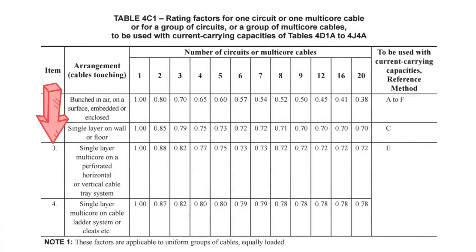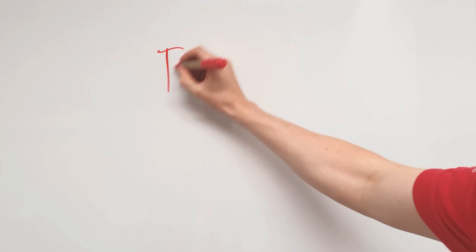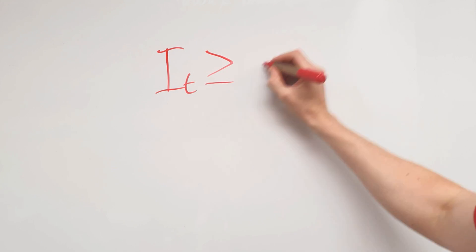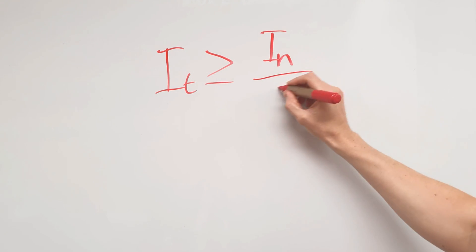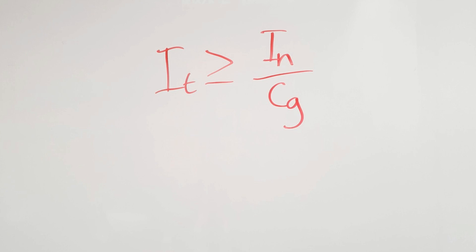...we look at item three of Table 4C1 in the wiring regs and track across to find the column marked eight. Looking at where they intersect, we've got a value of 0.72. Now this factor goes into a calculation that helps us determine conductor size, and it looks like this: It must be greater than or equal to In divided by Cg. In this formula, It is the tabulated value of current that the cable can carry — 'tabulated' just means in a table. In is the nominal rating of the circuit protective device, and Cg is the grouping factor that we just found.